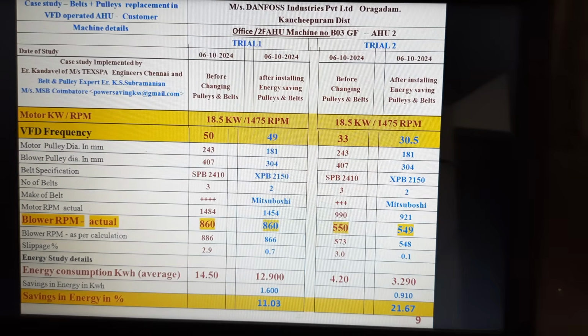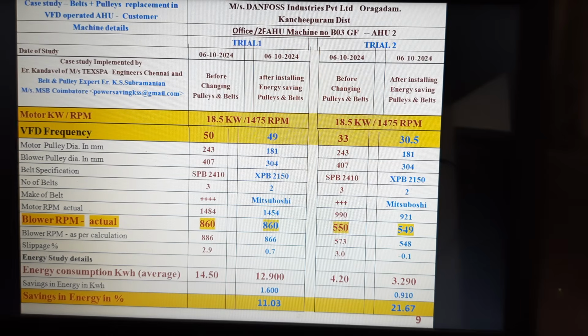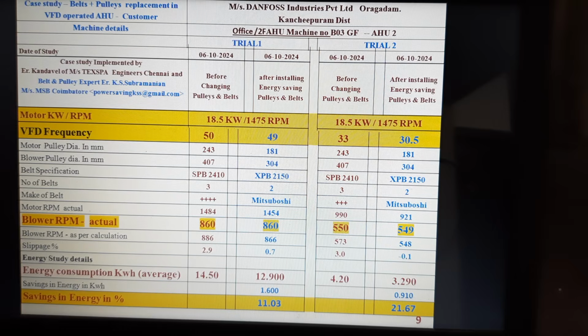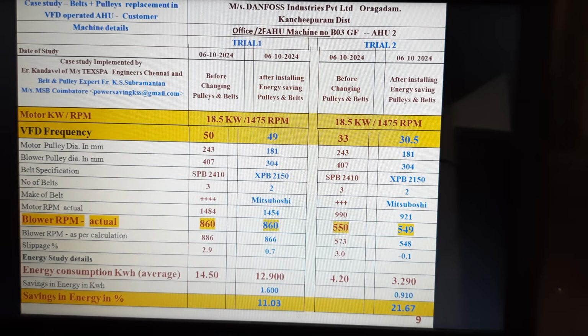Coming to the next case study, this was done at Danfoss, the VFD major, an international major based at Chennai. It is again on an air handling unit. It was done in the year 2024 by our MSB team, on an 18.5 kilowatt, 25 HP AHU blower, and we should appreciate Danfoss. They did two types of study: what the savings are at 50 Hertz, and what the savings are at 33 Hertz.